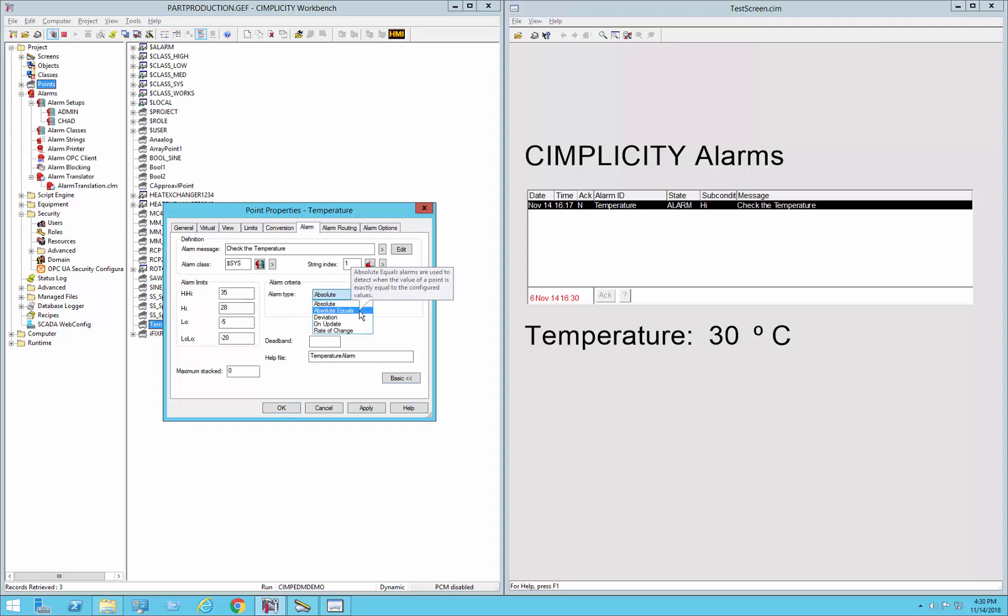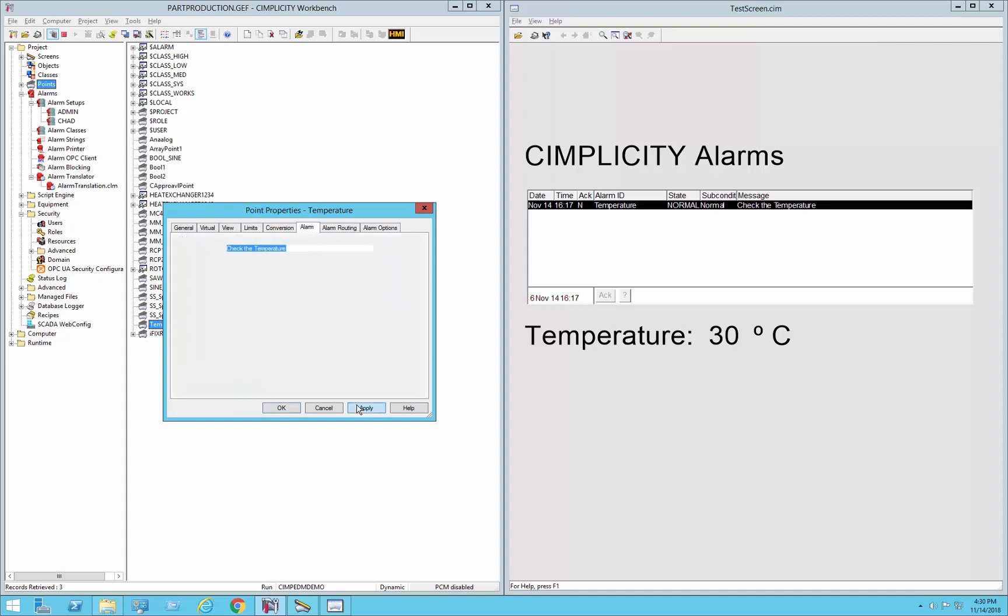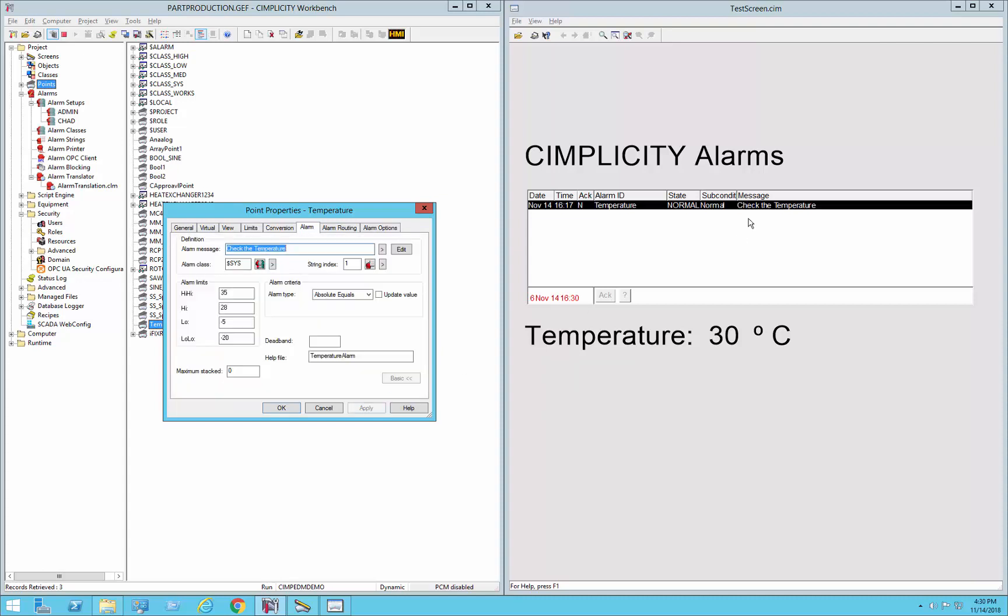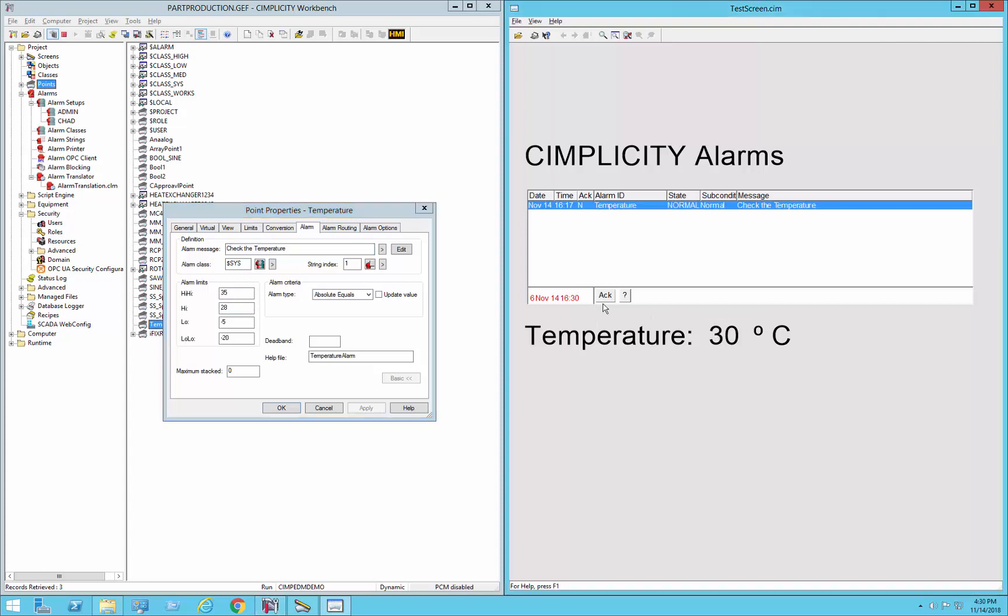Next in the list is called absolute equals. This is very similar, just that the only difference being that it checks for the exact value in these limits and uses that to put it in or out of alarm. So you can see if I hit apply now, that alarm over here, which was in alarm because it was above 28 and below 35, is now not in alarm because 30 degrees isn't exactly 28 or 35. So it's in normal state. So if I select that alarm and acknowledge it, it'll go out of alarm.